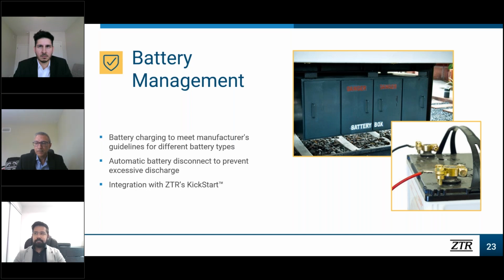Control systems should have battery charging that meets manufacturer guidelines for different battery types - current limits to prevent gassing, overheating, and sulfuric acid gassing, which is a health hazard, and voltage limits to ensure adequate charging whether in bulk, float, or absorption stage. Proper charging extends battery life and improves locomotive starting performance. Battery disconnect...